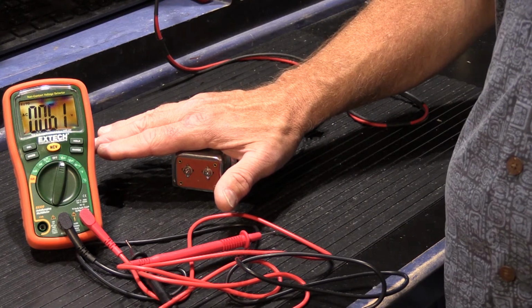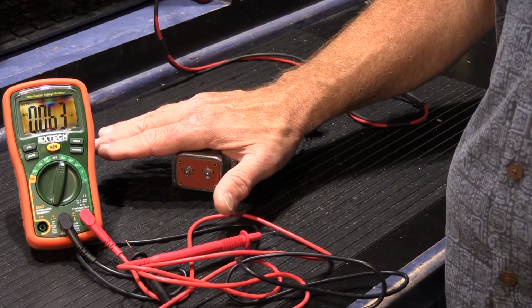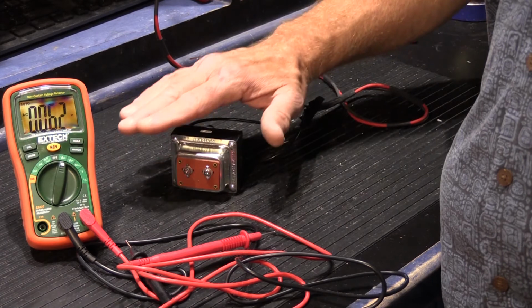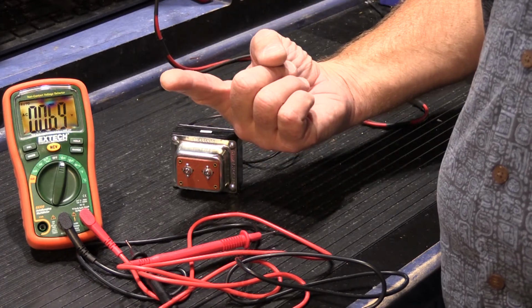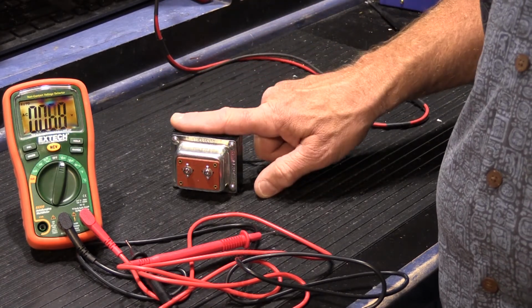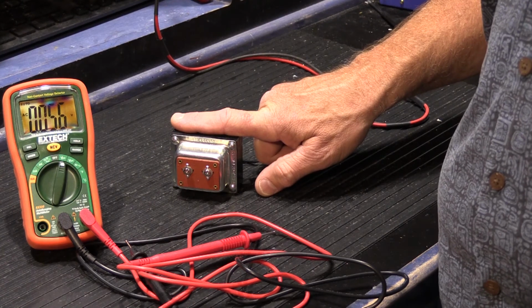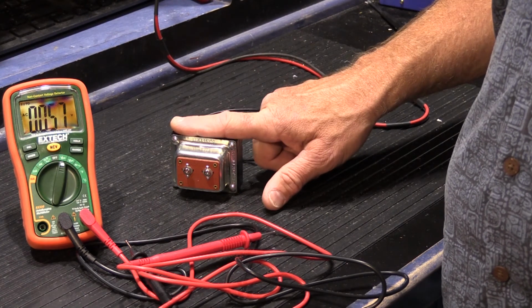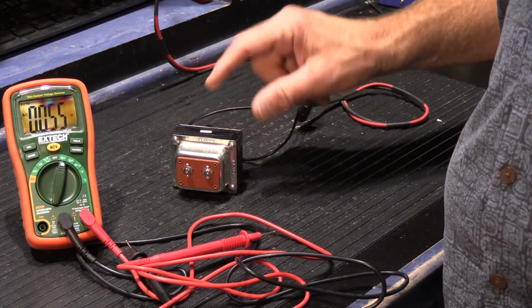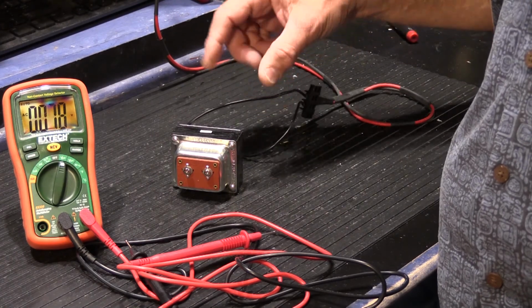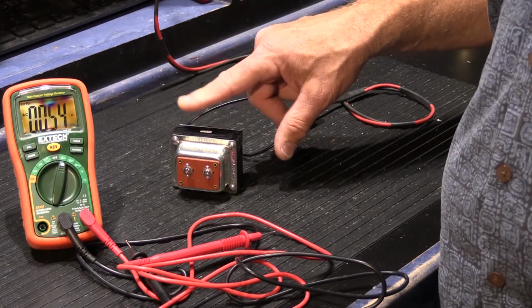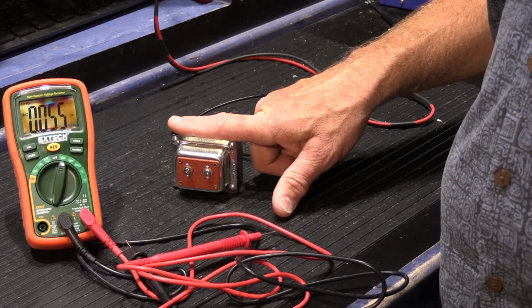If you open up your intercom master station and put your hand on the transformer and it's hot, here's how I always describe it to people: there are 3 conditions of transformers. First condition is stone cold — you put your finger on it and it's as cold as can be. That's a transformer that's probably turned off, either there's no primary voltage coming into it, or the transformer has failed and is dead.